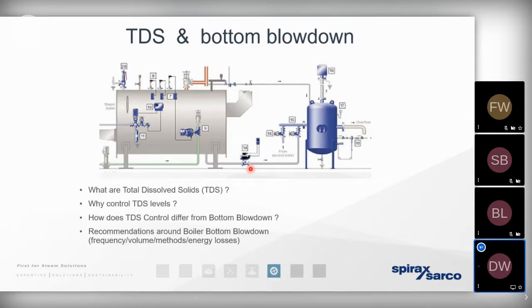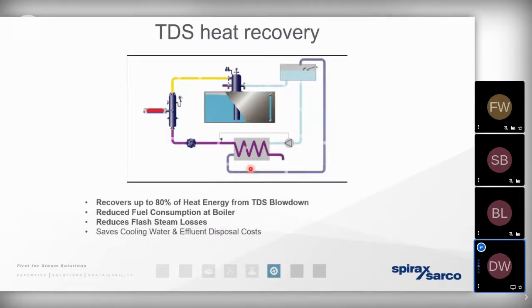So we want to recognize the benefits of moving away from a manual TDS system to an automated TDS system. That's typically operated by having a conductivity probe that sits in line ahead of a modulating valve, so it can be constantly drip feeding the exact prescribed mass of hot water to waste. But we know that the bottom blowdown has a lot of sediment in it, so it does need to go to waste. Whereas with the TDS, the solids are dissolved. So that hot water that goes to waste is in an excellent condition for heat recovery once it's gone across a simple heat exchanger. A typical TDS heat recovery solution can enjoy a very, very attractive payback that is very, very easy for us to measure for our clients.